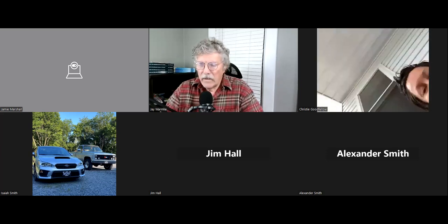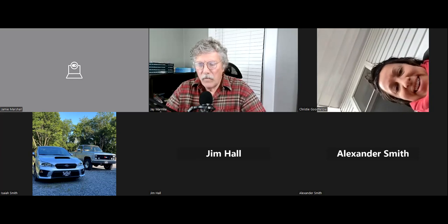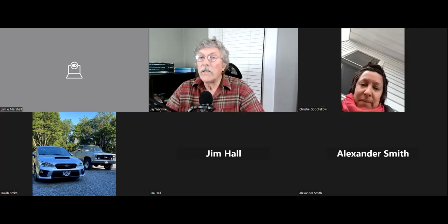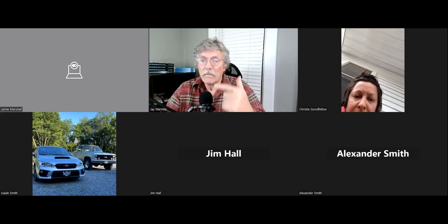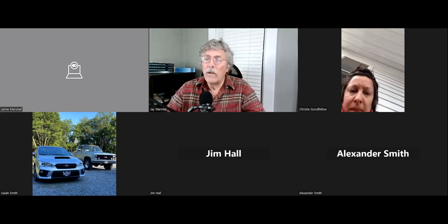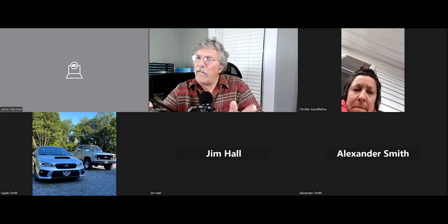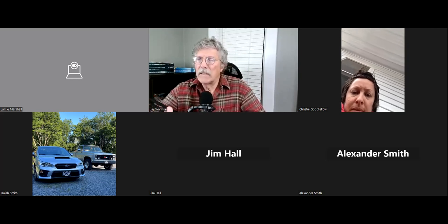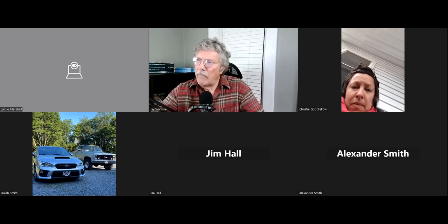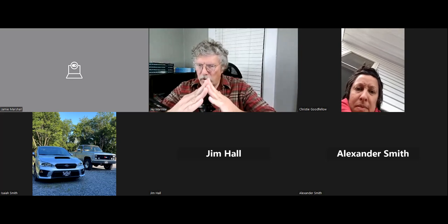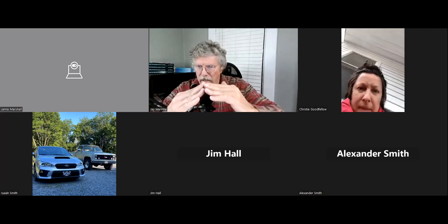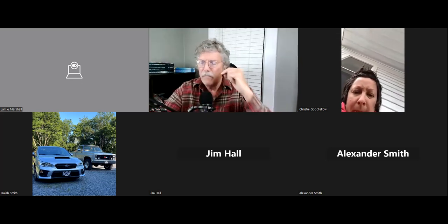All right, another thing with the rooftop mount, you're going to want to make sure that you give enough access. The rule is that you want 3 feet of clear walking space on each side and at the top of the array. So we're assuming it's a regular old pitched roof. Could be a shed roof or it could be a pitched roof like that.